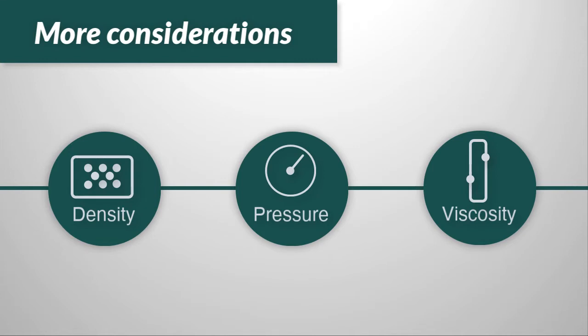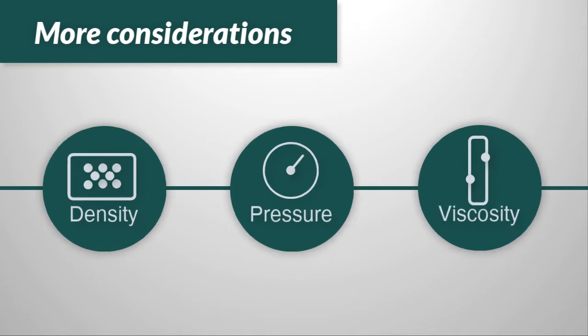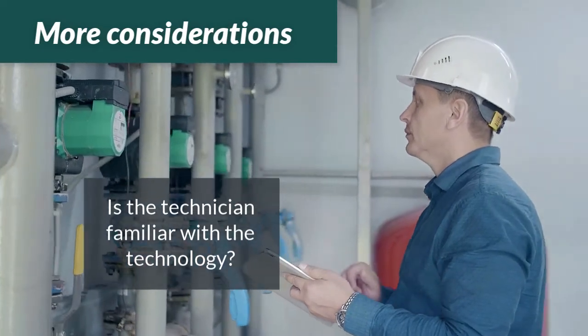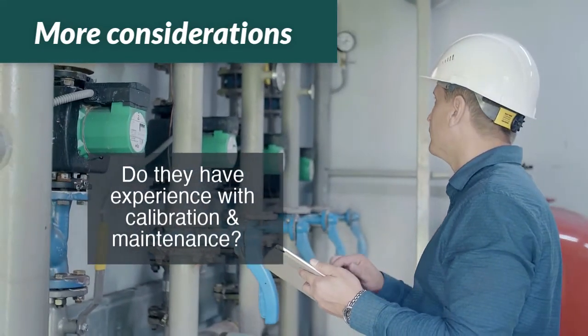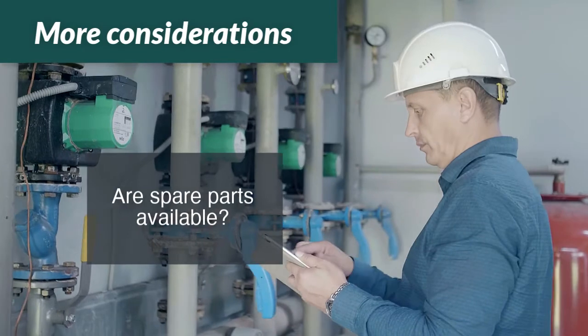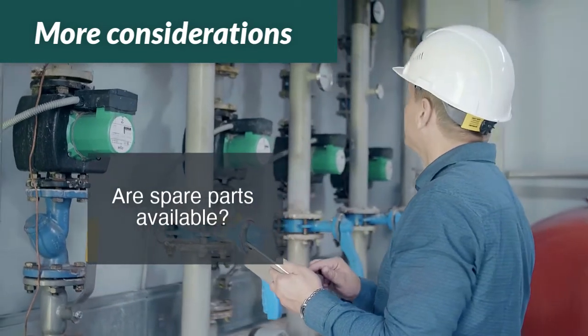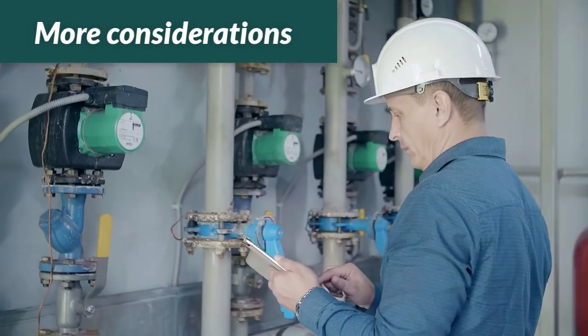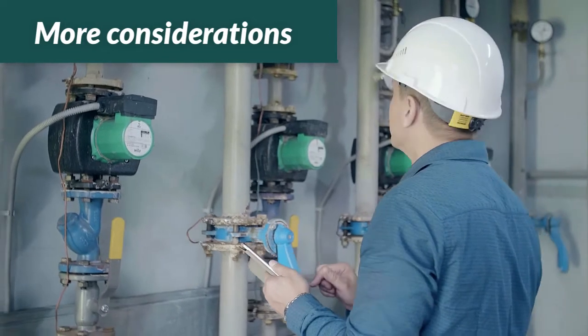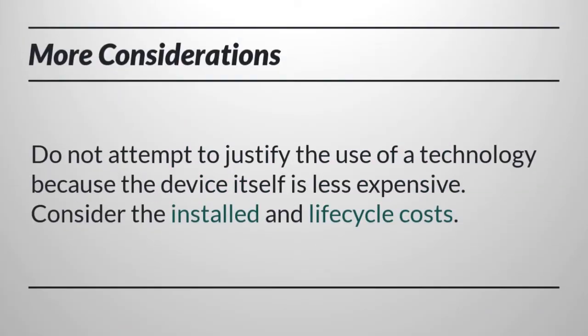Also consider intangible factors, such as the technician's familiarity with the technology, their experience with calibration and maintenance, and spare parts availability at the site. The cost of the installation should be computed only after taking these steps. One of the most common flow measurement mistakes is attempting to justify the use of a technology because the device itself is less expensive. Consider installed and life cycle costs.